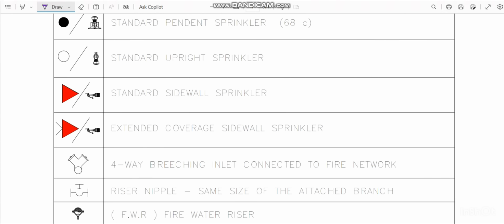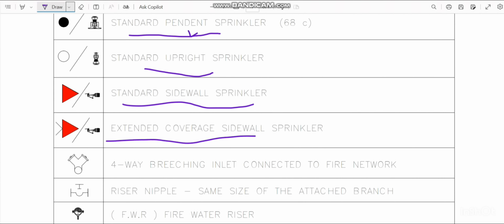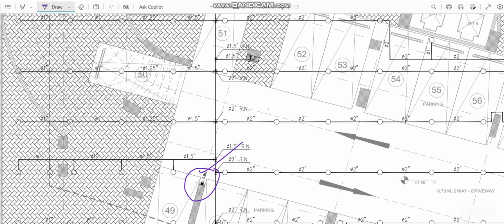Then we have four types of sprinkler used for this project. First one is the standard pendant sprinkler. Pendant sprinklers, as you know, we normally use for ceiling applications. Where we have a ceiling, there we use the pendant sprinkler. And upright sprinklers we mostly use for the car parking where we don't have a ceiling. And then the standard sidewall sprinkler and the extended coverage sidewall sprinkler. So these four sprinklers we have used for this project. We will see what is there.